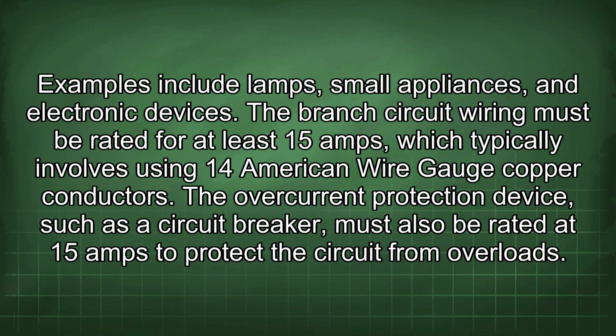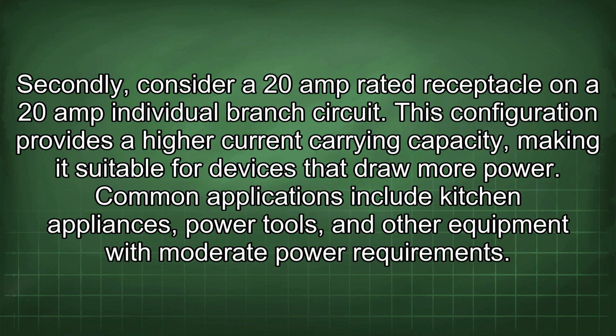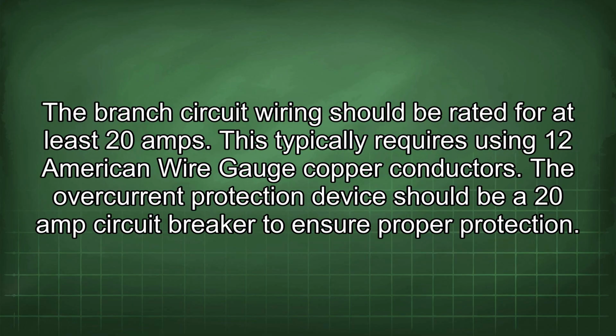the circuit from overloads. Secondly, consider a 20 amp rated receptacle on a 20 amp individual branch circuit. This configuration provides a higher current carrying capacity, making it suitable for devices that draw more power. Common applications include kitchen appliances, power tools, and other equipment with moderate power requirements. The branch circuit wiring should be rated for at least 20 amps. This typically requires using 12 American wire gauge copper conductors. The overcurrent protection device should be a 20 amp circuit breaker to ensure proper protection.